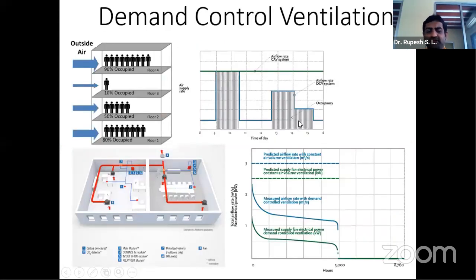Then demand control ventilation. I think this is very important in typically large commercial spaces where there are so many rooms and so many AHUs, so many zones which are operating at different temperatures, different occupancies, different humidity levels, different activity levels. When we have a demand control ventilation system, we could achieve this in the same building. When I have, let's say, 5 floors or 10 floors or even 25 floors, one floor may be 90% occupied, one may be 10% occupied, one may be 50%, and the amount of outdoor air that I need to condition and push into my building could vary across each floor or even across each room.